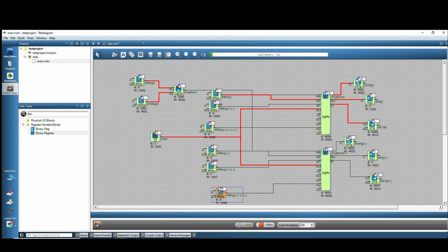You can receive this information from the block outputs. So, we have the chance to observe how many seconds it stayed in error. Until when? The block stays in error until a trigger comes to the error reset input. We send a trigger to the error reset input, and the aging member block becomes active again. And it waits for the working information within 40 seconds. This time we gave a trigger to the working information. So, we ran both aging member blocks at the same time.